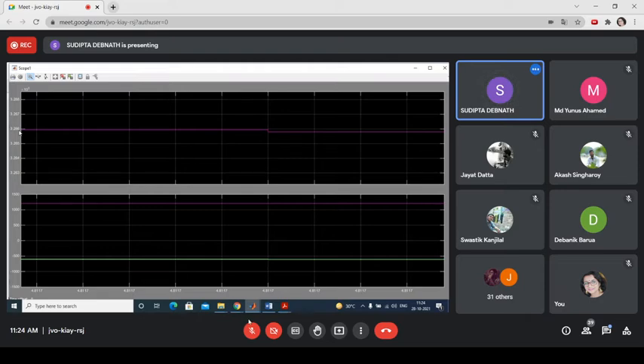Is it clear? So it is 326.6 kV, and this is the sending end voltage. We will not check the sending end current now, because under surge impedance loading, we know that sending end voltage and receiving end voltages are equal, since reactive power generated equals reactive power absorbed. Please note down this voltage, 326.6 kV. Vs is 326.6 kV.